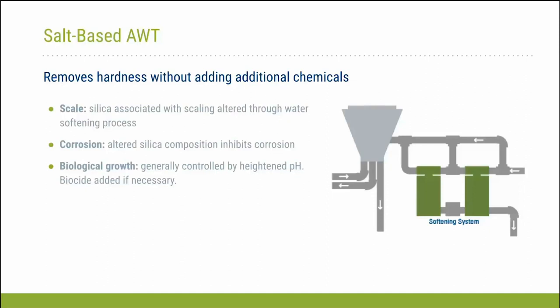So just a high-level explanation of how this system works. Over on the right-hand side, you're going to see 2 green boxes, and those are essentially alternating regeneration and brine tanks. Again, this is a chemical-free water treatment system. Those 2 tanks are essentially treating the incoming water into the cooling tower. You can get a detailed explanation of how those are working within the report. On the left-hand side, it's giving an explanation of how scale, corrosion, and biological growth are controlled with this system.